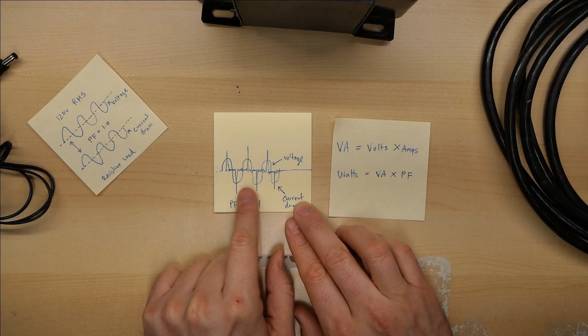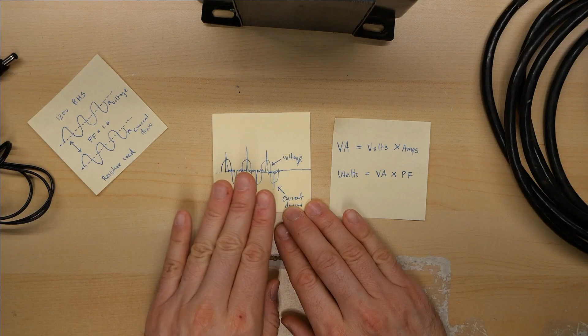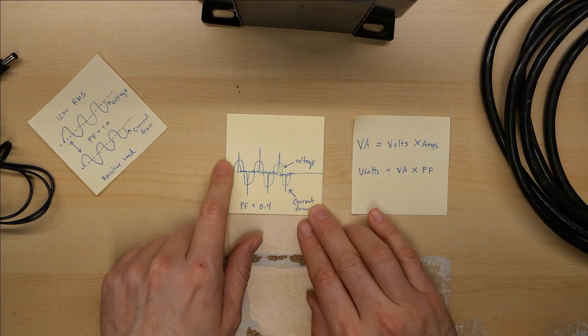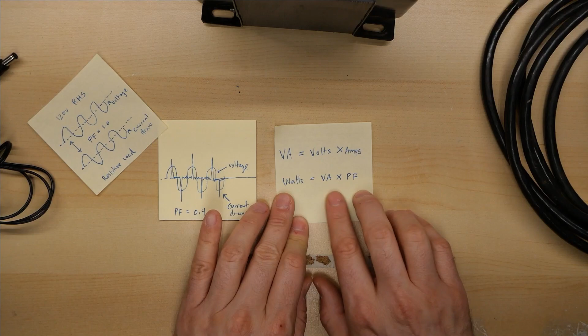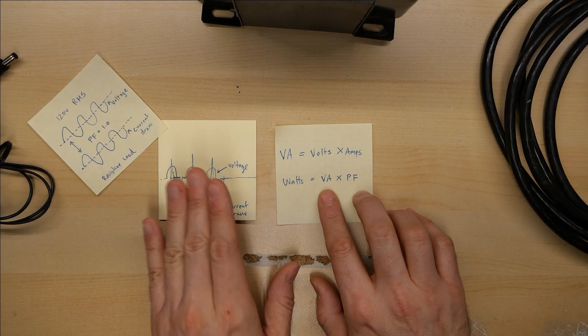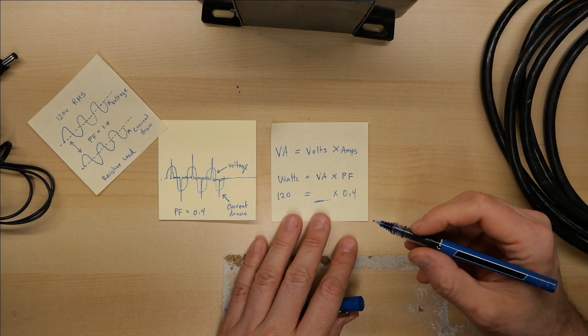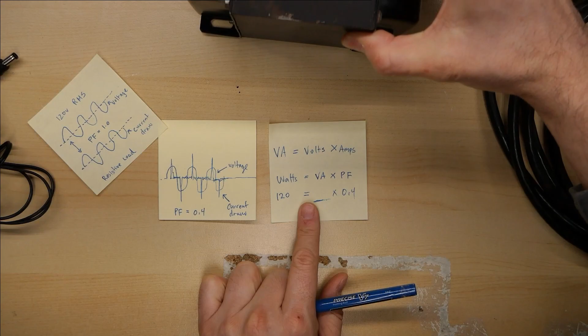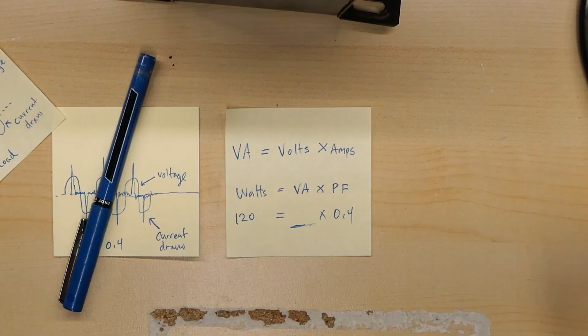Imagine my theoretical power supply hooked up to this isolation transformer is running at 120 watts. Because it's not a resistive load, it's not 120 VA. Since the current waveform is very spiky, let's theoretically say we determine the power factor is actually 0.4. Going back to the calculation, we can solve for the number of VA that our 120 watt power supply with a bad power factor of 0.4 actually uses. We know we have 120 watts, that's what it says on the label, and the power factor is 0.4, and we need to solve for the VA so we can make sure this device won't exceed the capacity of my isolation transformer.